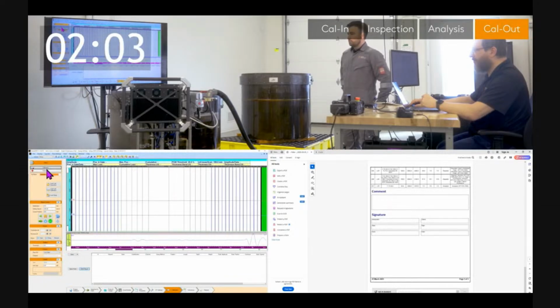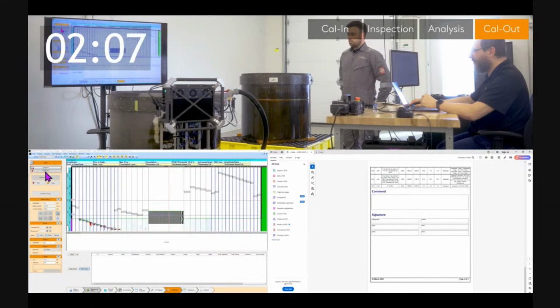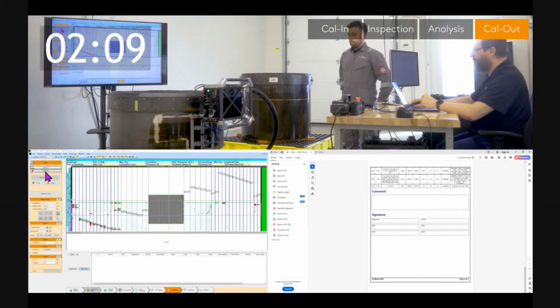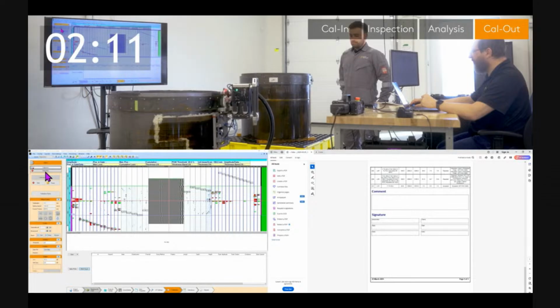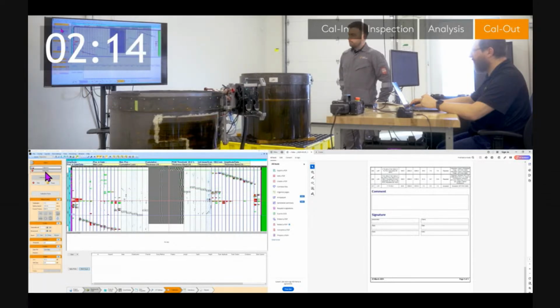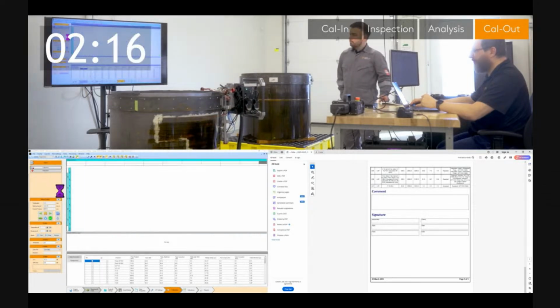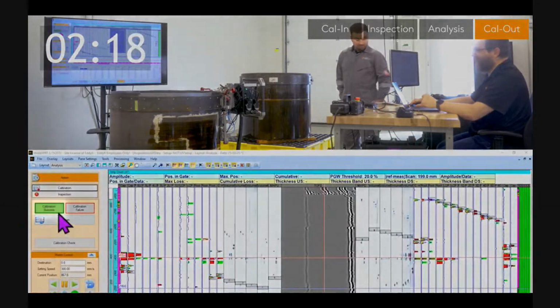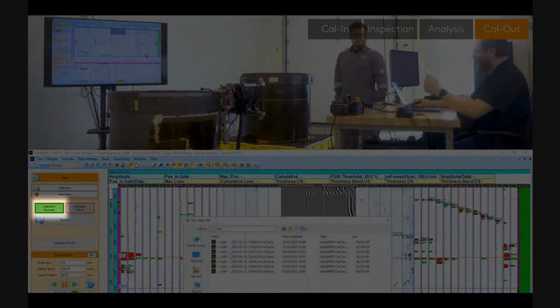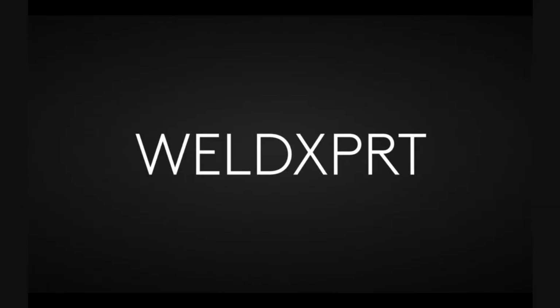We're back in position on the cal block. You'll see the strip chart running with the gray boxes looking for the relevant positions of the reflectors it knows in the calibration block. If they're all in the right place with the right sensitivity and time of flight, we get the green calibration success, and we complete the sequence, ready to move to the next weld for inspection. That total cycle time for that calibrate in, inspection, analysis, report, and calibrate out is 2 minutes and 18 seconds.